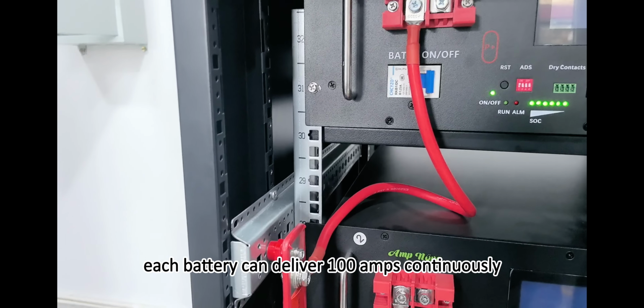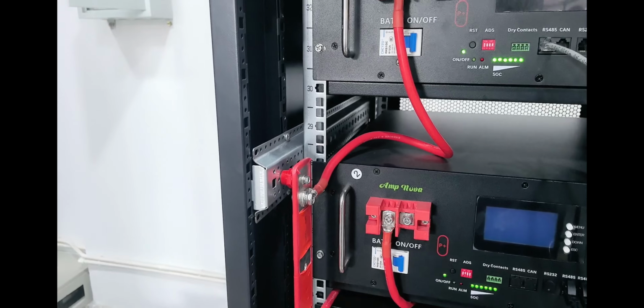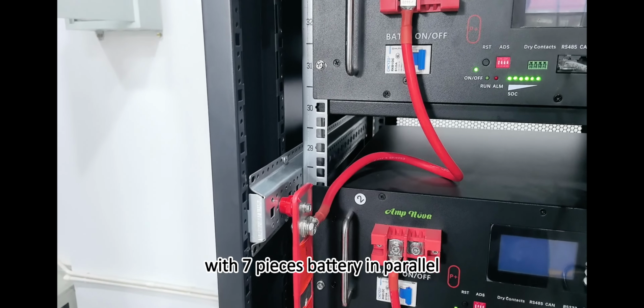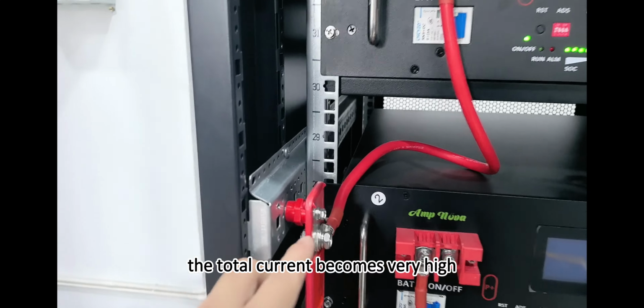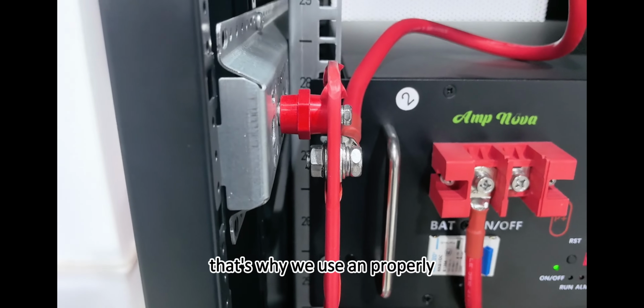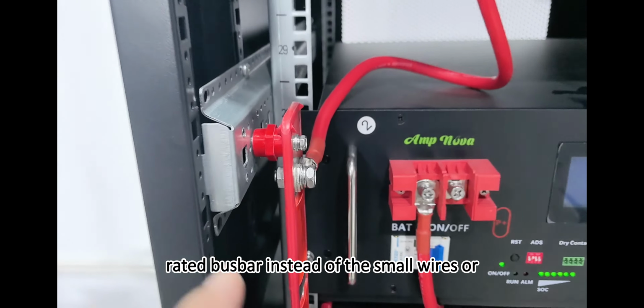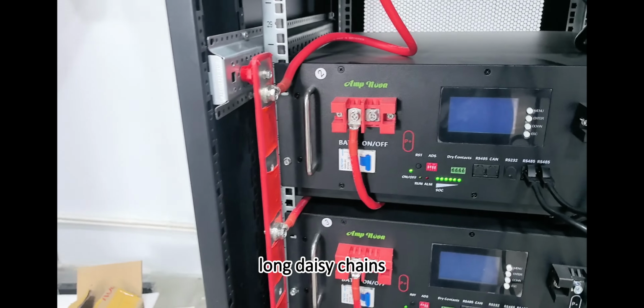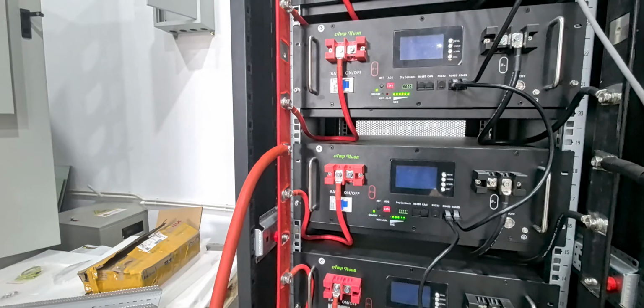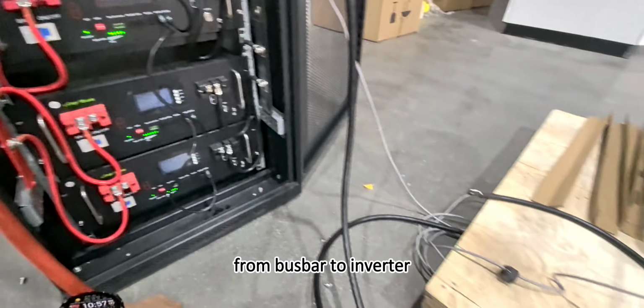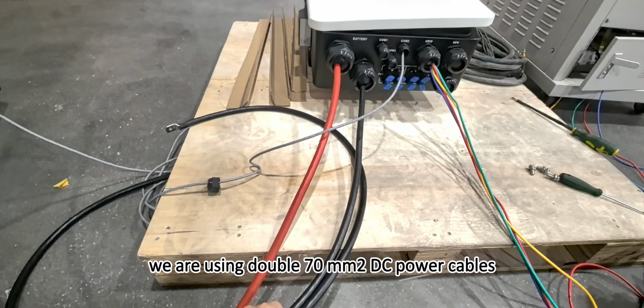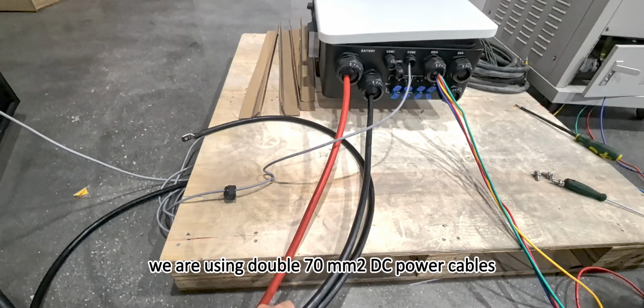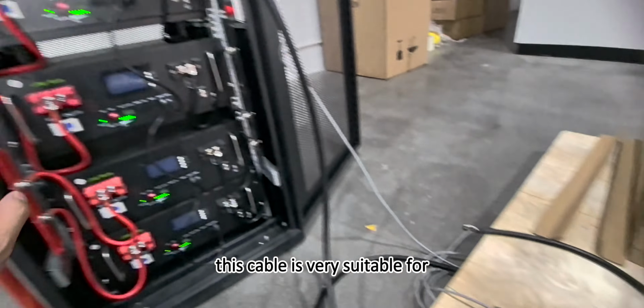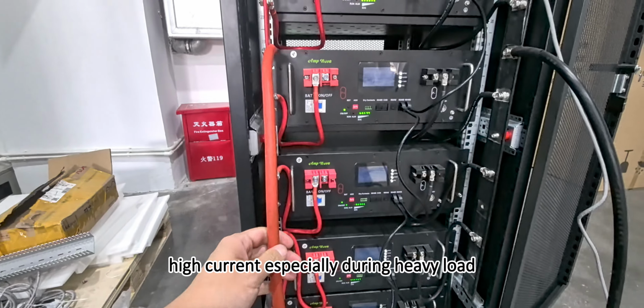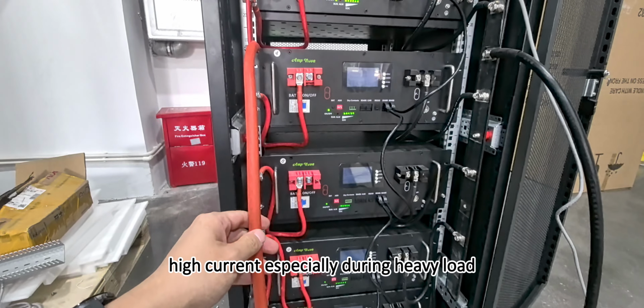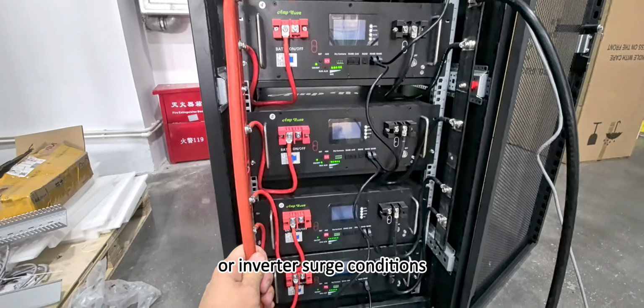Each battery can deliver 100 amps continuously. With 7 pieces of battery in parallel, the total current becomes very high. That's why we use a properly rated busbar instead of small wires or long daisy chains. From busbar to inverter, we are using double 70 square millimeter DC power cable. This cable is very suitable for high current, especially during heavy load or inverter surge conditions.